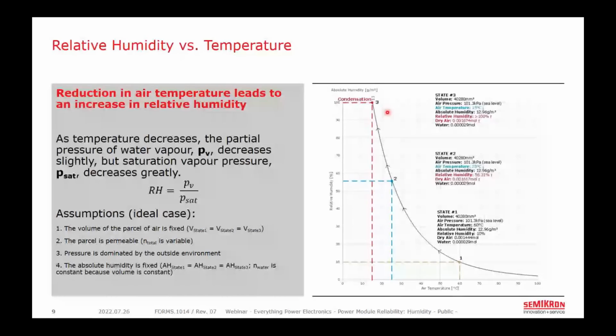Now, in real world systems, this behavior is a little more complex because the absolute humidity will actually change as the temperature changes. So we're not stuck perfectly moving along this line. And it's actually something called the specific humidity or mixing ratio that remains constant. But the basic relationship between relative humidity and temperature remains. The statement we want to emphasize is this one in red here, that a reduction in air temperature leads to an increase in relative humidity.